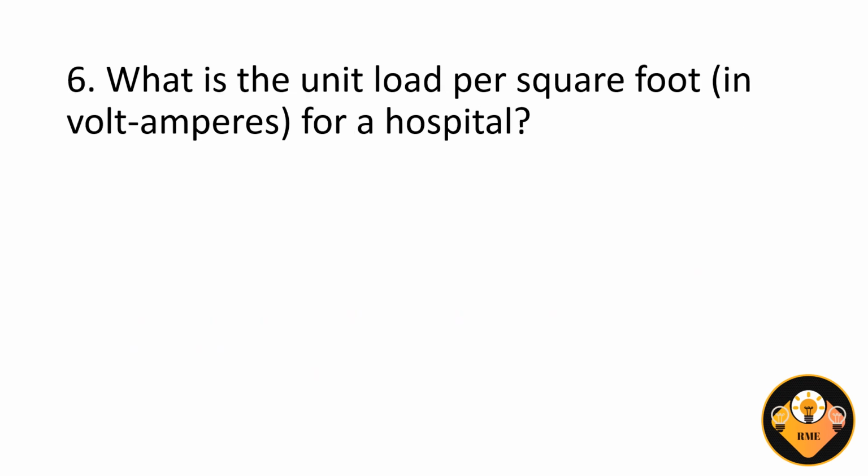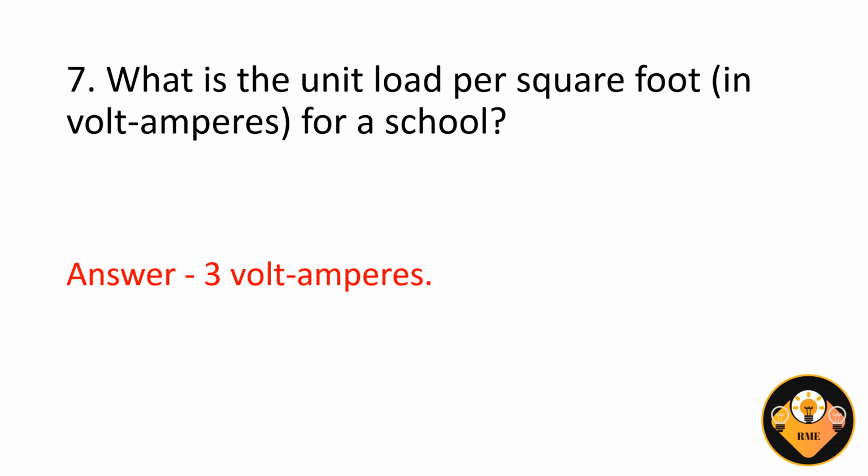Number 6. What is the unit load per square foot, in volt-amperes, for a hospital? The answer is 2 volt-amperes. Number 7. What is the unit load per square foot, in volt-amperes, for a school? The answer is 3 volt-amperes.